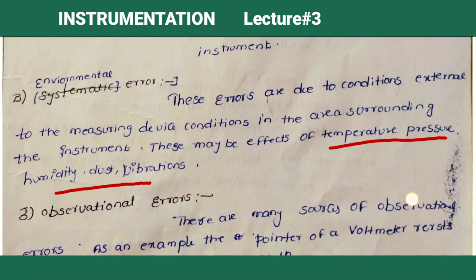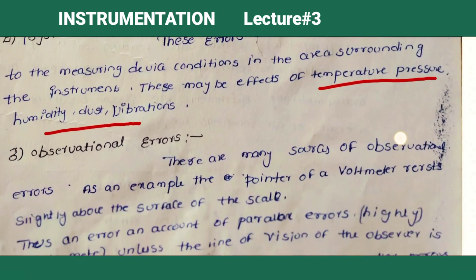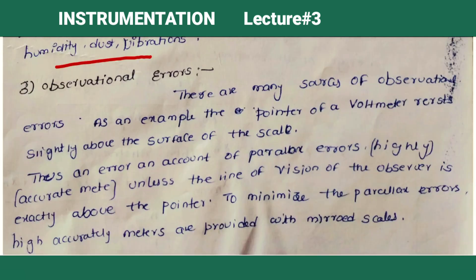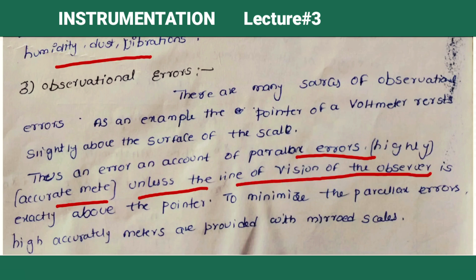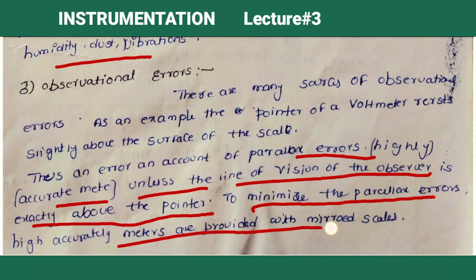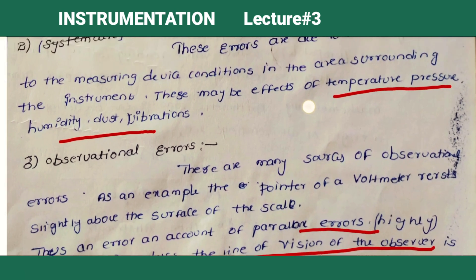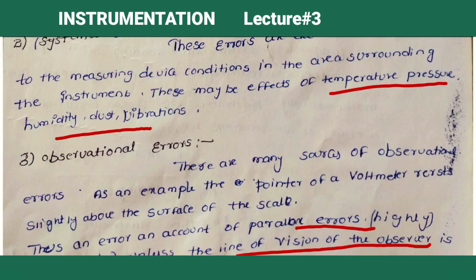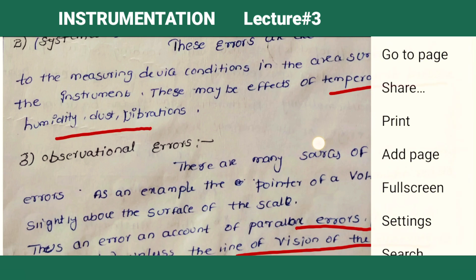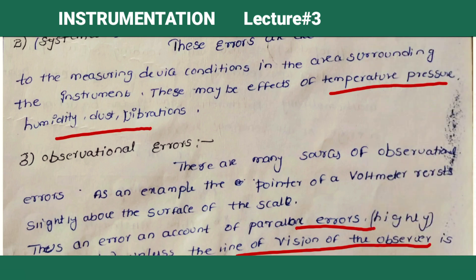Observational errors include parallax error — due to the observation angle of the person. For example, the pointer of a voltmeter: if you view it from one side, there may be a change in reading. A parallax error is an example of observational error. To minimize parallax error, meters are provided with a mirror and scale. Environmental errors are reduced by using instruments in proper normal temperature conditions, and observational errors can be reduced by providing meters with a mirror scale.